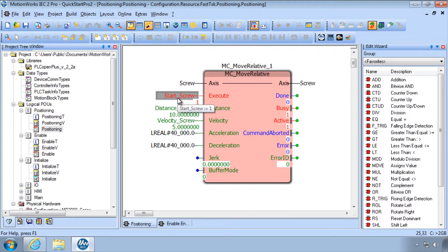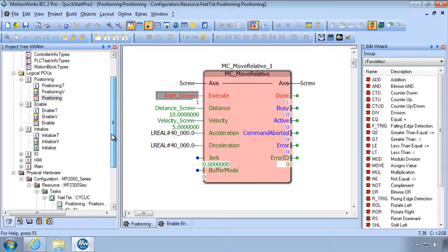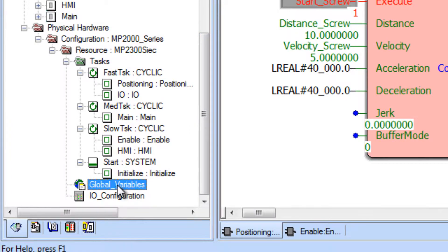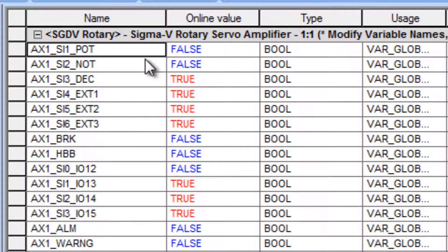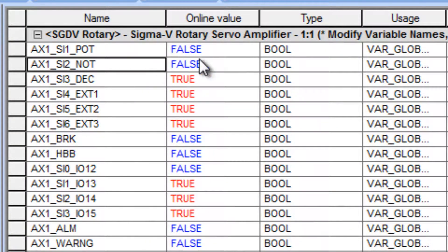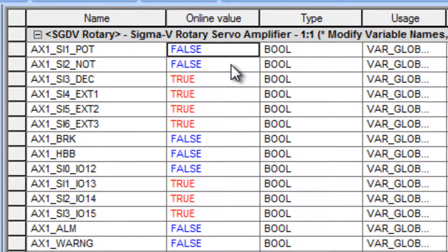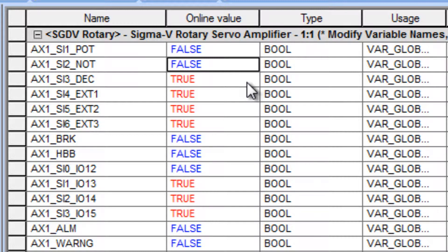An over travel condition will also prevent motion and cause Error 4370. The over travel input status can be seen in the global variables. They are referred to as POT and NOT — positive over travel and negative over travel. False means motion is allowed, and true means motion in that direction is prohibited.